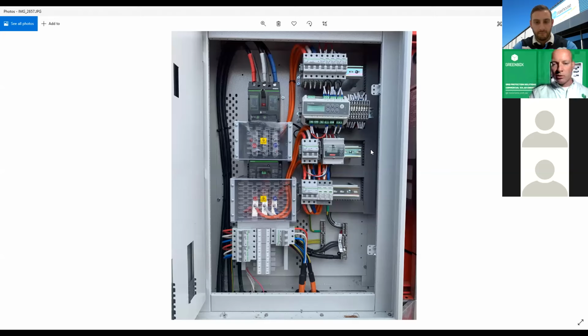For us electricians, of course, it's easy. We've got the main switch here, your main isolator - you connect straight away to the top. You've got your nice cable rack here, so you can cable tie your cables neatly into this board and make it fit perfectly. Your neutral and earth bar are right down here at the bottom, and as I mentioned, your distribution board is for your inverters to hook up - you can connect up to a maximum of 6 inverters. Don't worry if you're using a larger inverter needing an 80 or 100 amp breaker - we just change over the chassis rail so the bigger breakers fit in there.